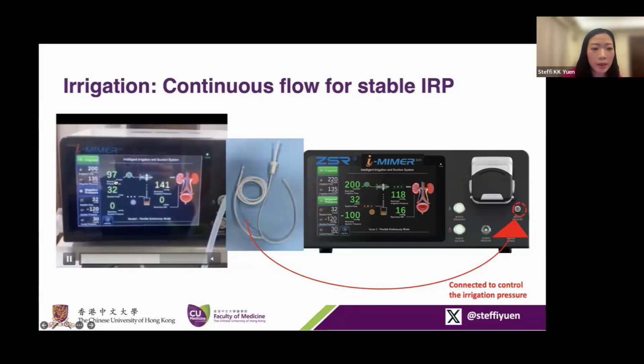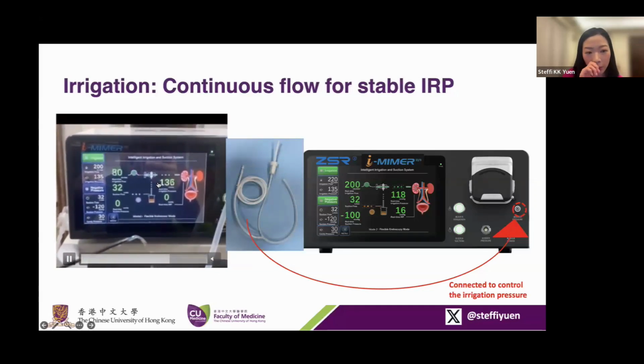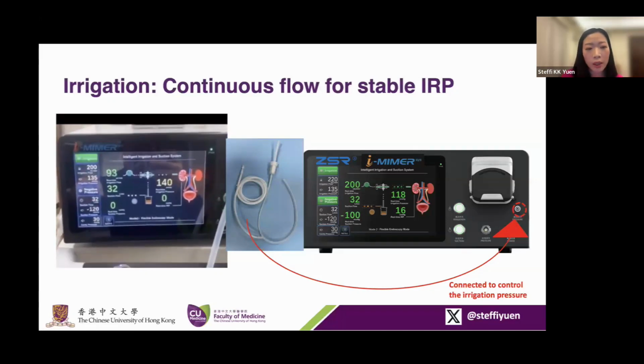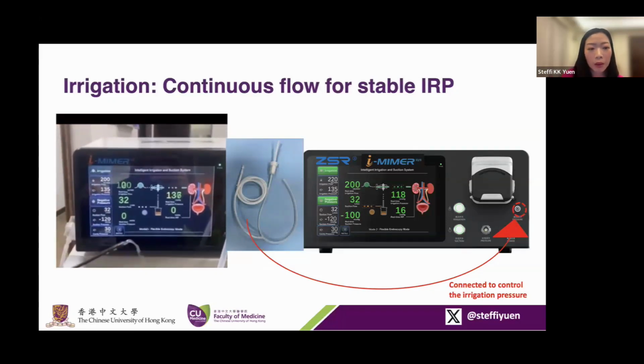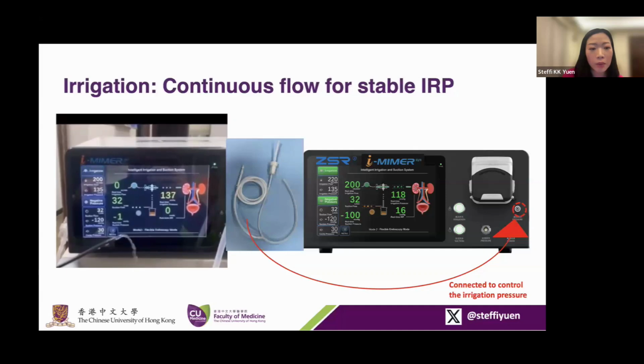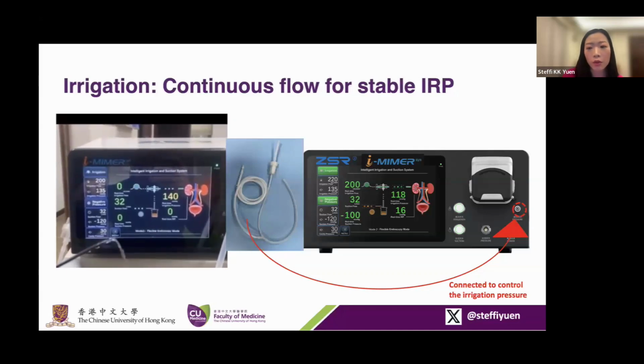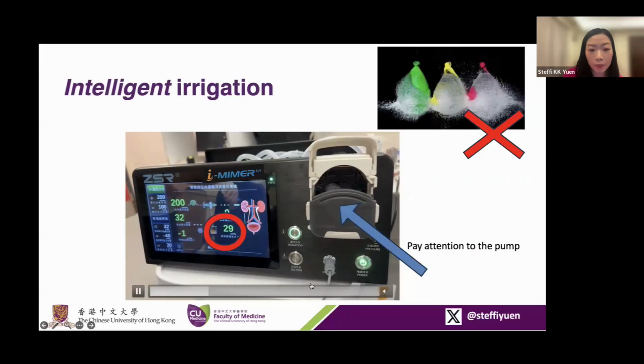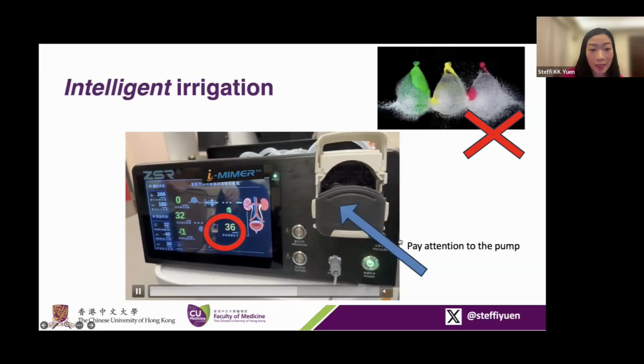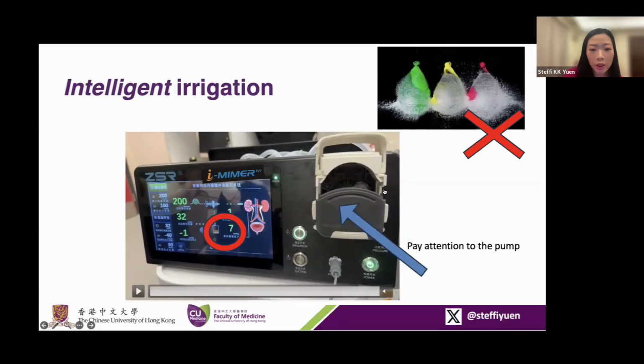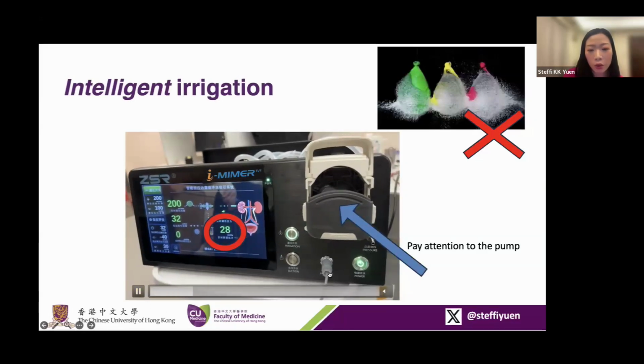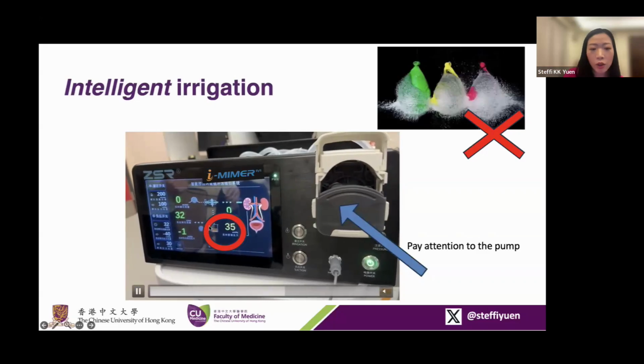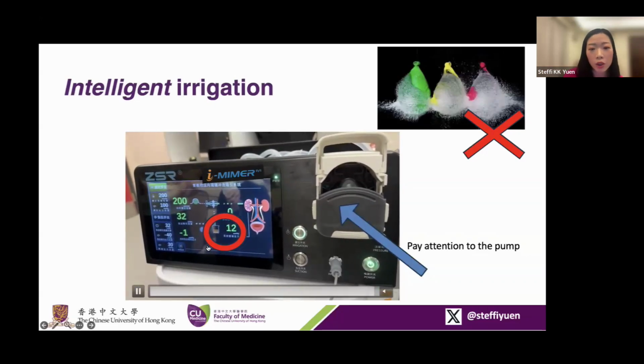You can see that the values keep jumping around in the middle of the screen because it's regulating and keeping the pressure at a safe range within 30 millimeters mercury. It acts with a pump and an algorithm. So it's intelligent because when you're connected to the IRP sensor, you can see at the right lower corner there's a gray thing plugged into the pressure sensor. And the red circle shows the real-time pressure.